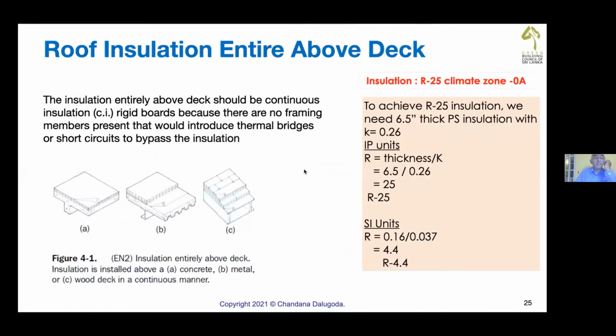Now quickly go through roof structures. There are 3 types of roof structures available. One is roof insulation entirely above deck, that is concrete roof. Now I have calculated the roof U value and the thermal insulation required for the Sri Lankan climate. Will you believe we need 6.5 inches thickness or 160 millimeter thickness polystyrene insulation, not 50 millimeter, remember, not 50 millimeter, for concrete slabs.